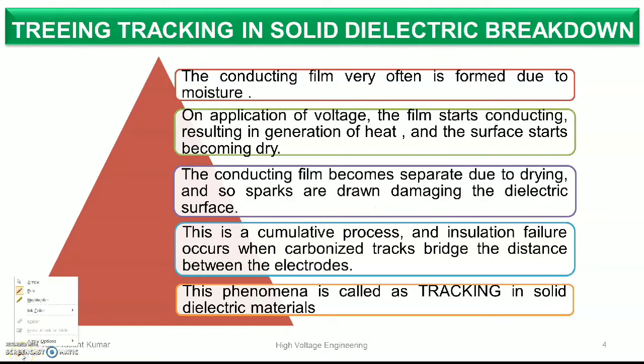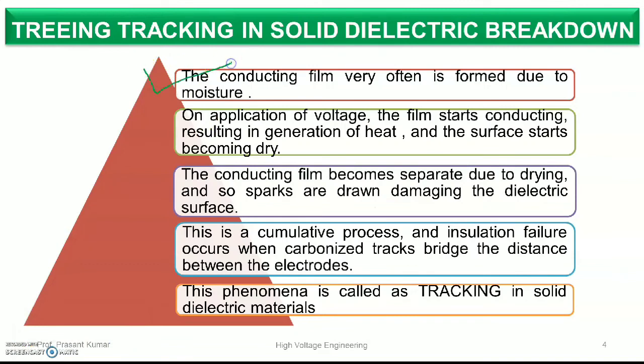The conduction film very often is formed due to moisture. If moisture is present, a conducting path develops. On application of voltage, the film starts conducting and results in generation of heat, and the surface starts to become dry. If any solid dielectric material has moisture, when we apply high voltage, due to the weaker dielectric strength, a smudged conducting path forms on the surface — and this is a cumulative process.